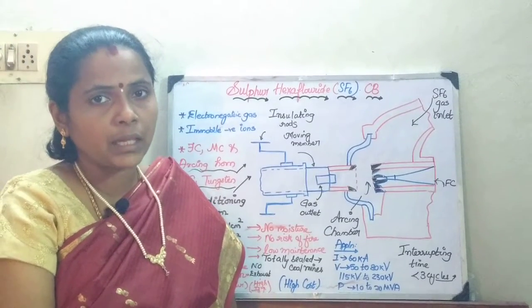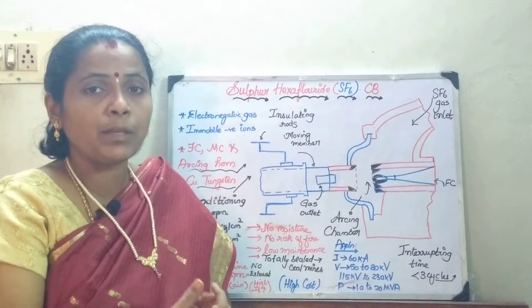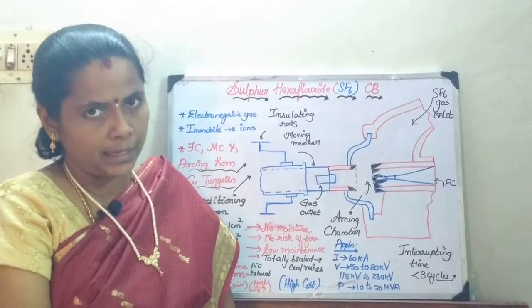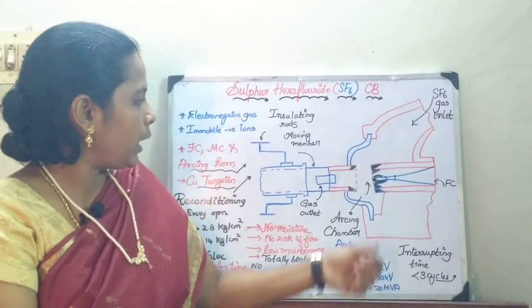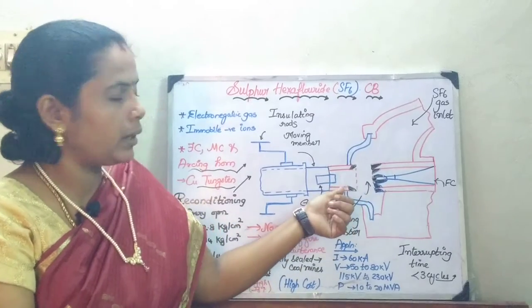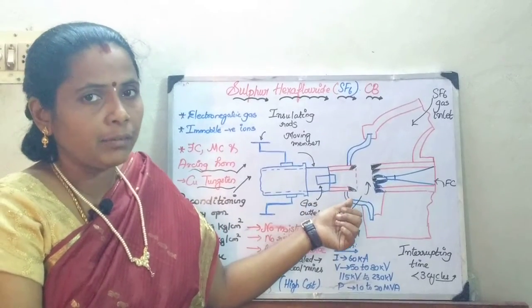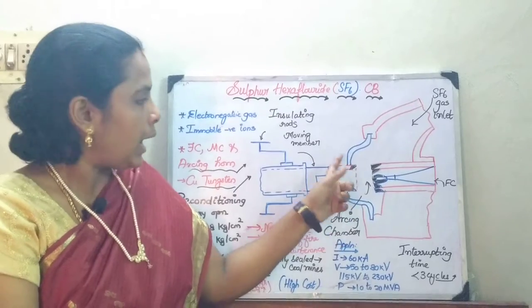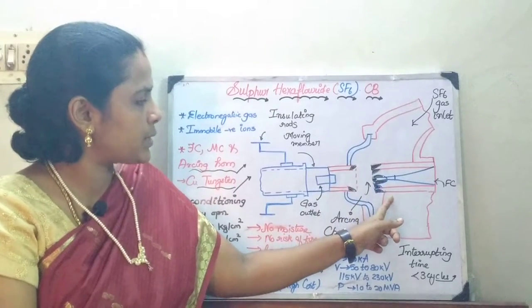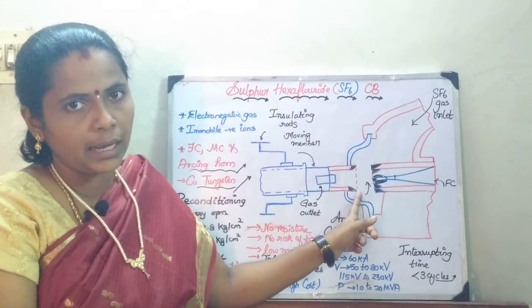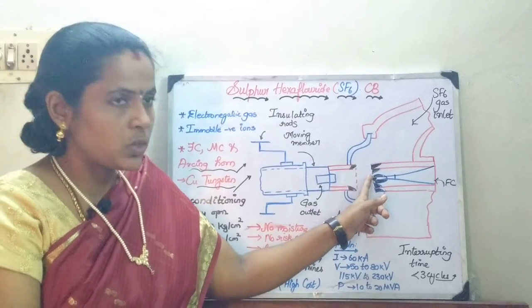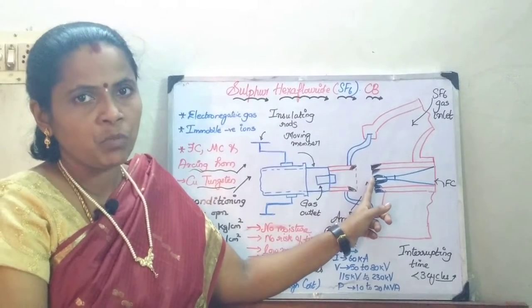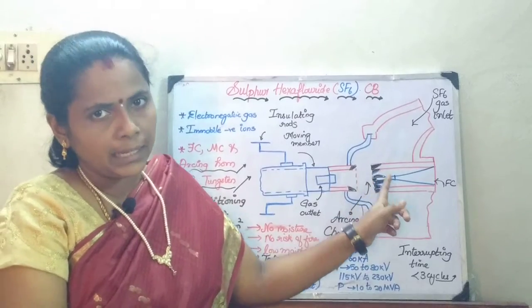When we say it has an electronegative gas, it has the capability of absorbing the electrons in the arcing path. In the circuit breaker, you are going to have a fixed contact and a moving contact, and under a fault whenever they get separated, an arc is struck between the fixed contact and the moving contact. Whenever there is a process of arcing, it is nothing but a conducting path of electrons.